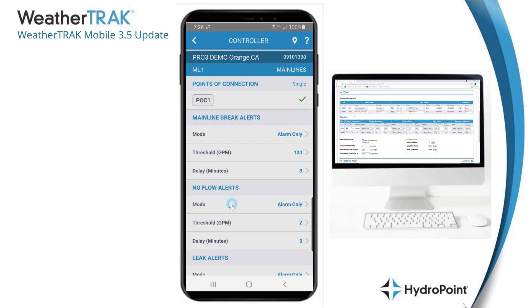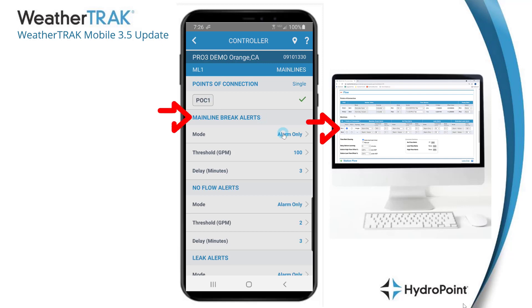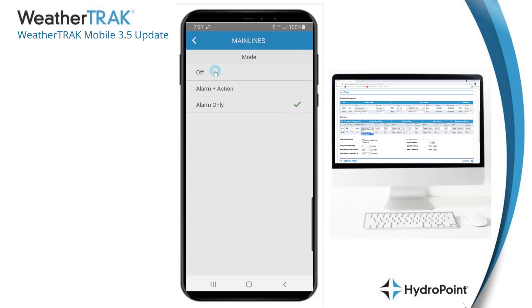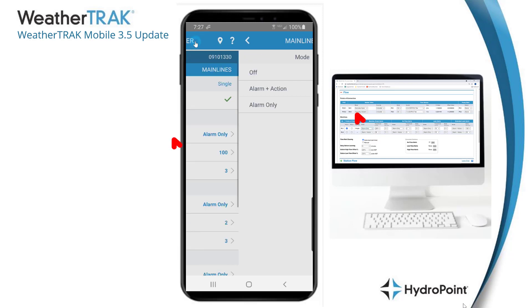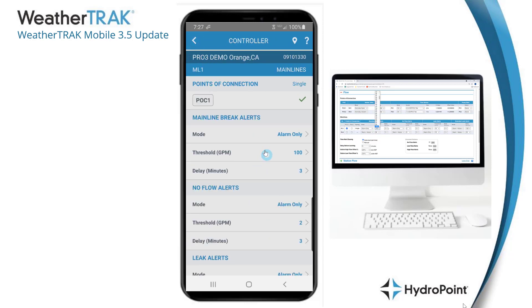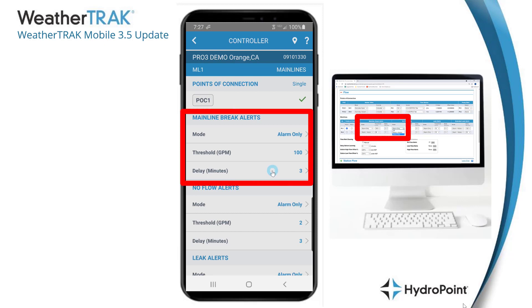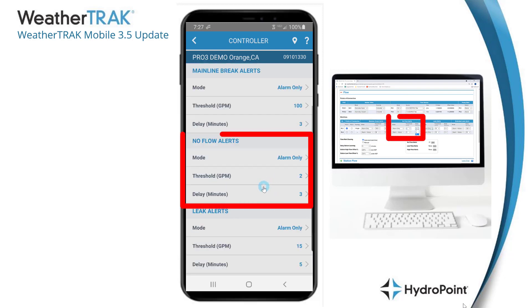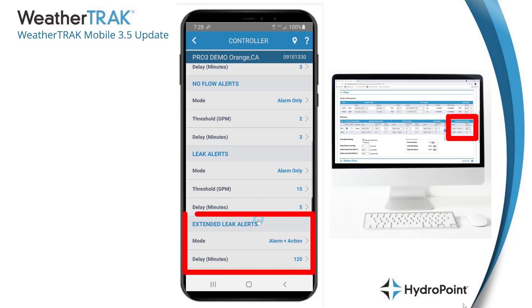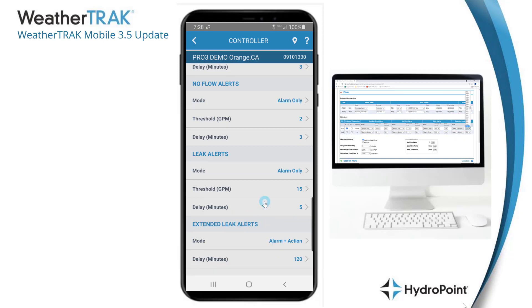Programming main lines is really about programming the alert thresholds the software should look for. When we go into program main line 1, there's a quick link to the point of connection information. On the main line programming page we set up main line break alerts with your mode — off, alarm only, or alarm and action — the threshold, which is the measured value that sparks the alert, and the delay that allows the system to balance out during transitions to eliminate false alerts. You then program all thresholds for main line break alerts, no flow thresholds, leak alert thresholds, and extended leak information.